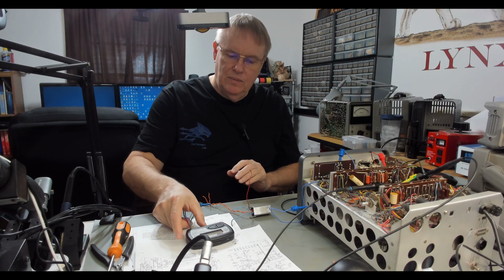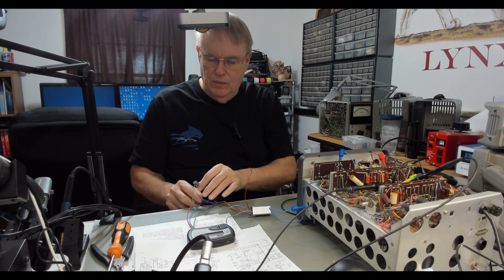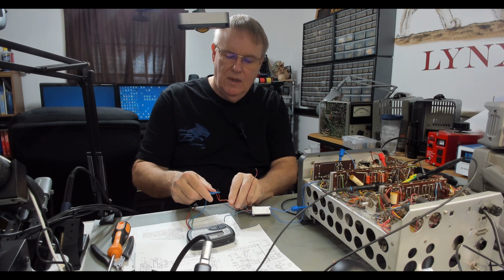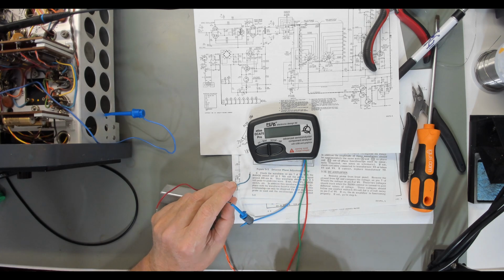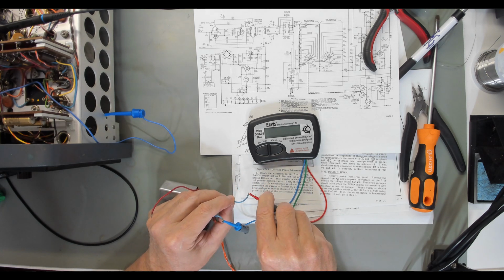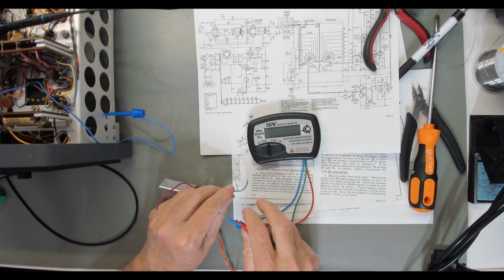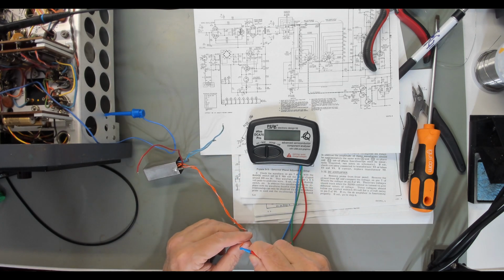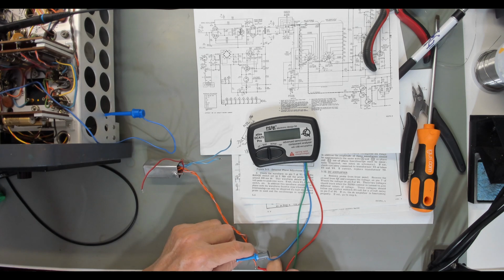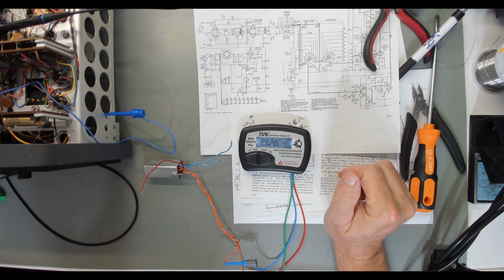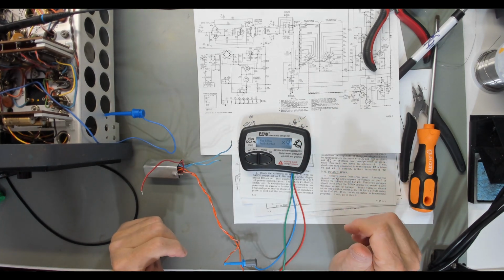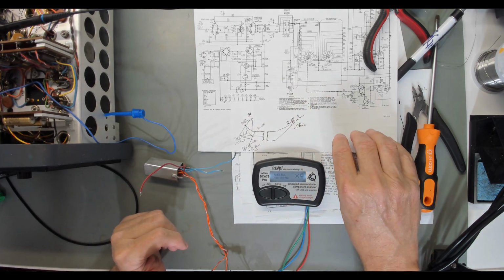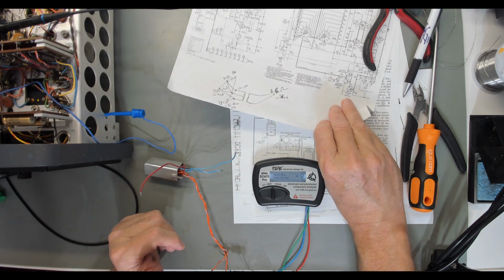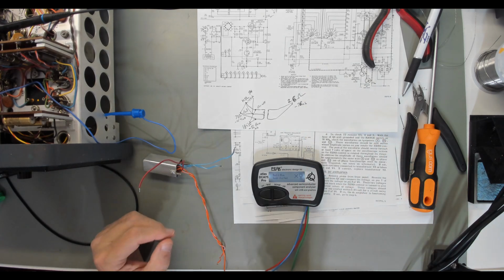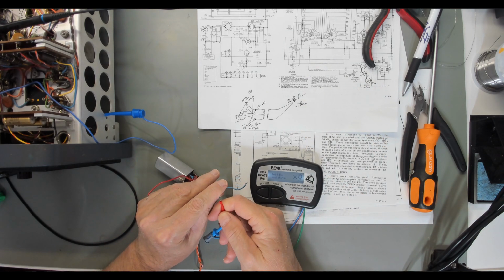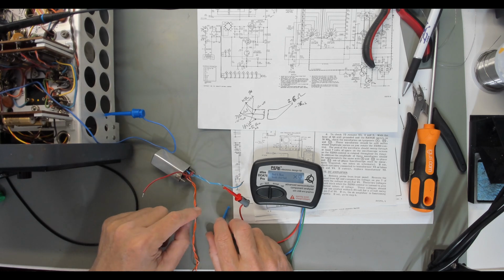So then I got my little Peak DCA75 component tester out and thought, well, let me do this. Let me hook it up here. Actually, let's start here. If I go over to the orange, the outputs, and I check that winding, which should just be a coil winding, I would expect, it tells me it's shorted. So 2.6 ohms is too low a resistance for it. It just says they're shorted. If I go to the blue and hook up the blue windings, and there's no short, by the way, between the blues and the orange.